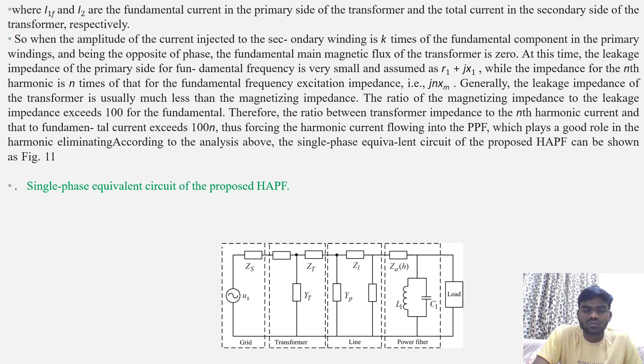The amplitude frequency characteristics of Zn and ZOS. It can be seen the output impedance of the proposed HAPF in the harmonic domain is capacitive and small. With the increase in frequency, the impedance decreases. Moreover, the variation of magnetizing impedance has little effect, as it mainly depends on the PPF. As the value of ZOS is small, the proposed HAPF has a good performance in harmonic eliminating. The parallel harmonic resonance can also be restrained.